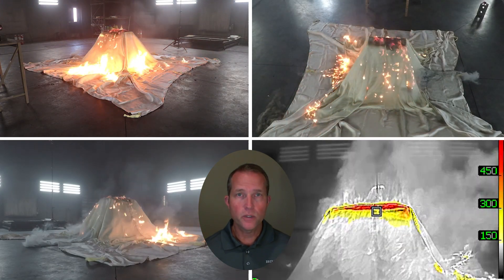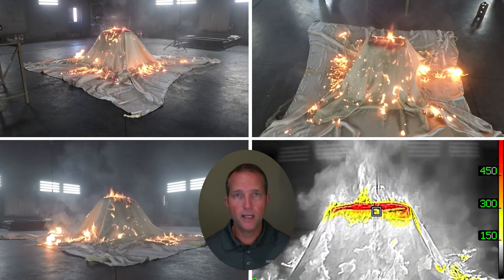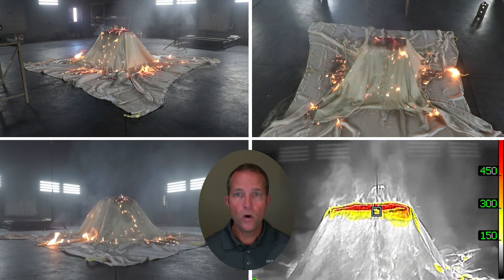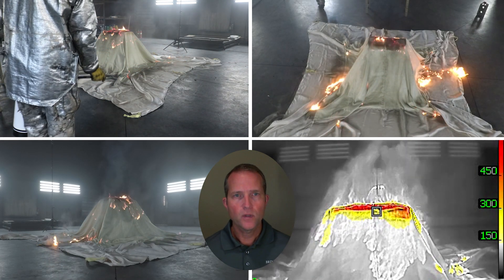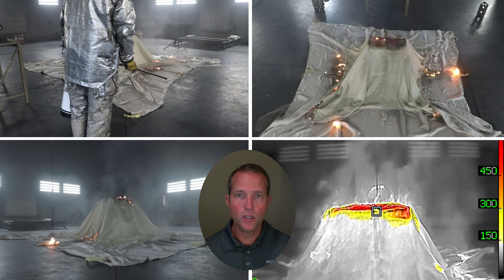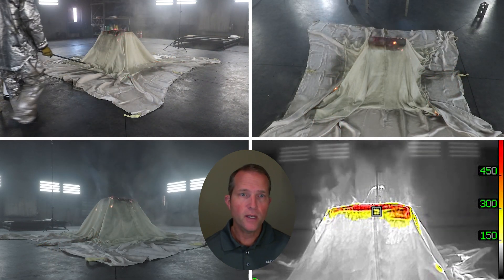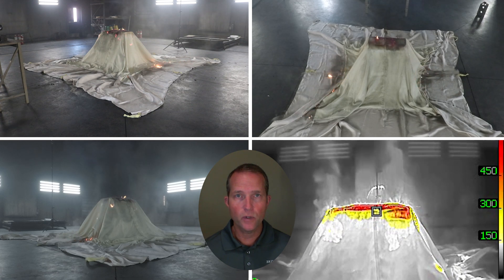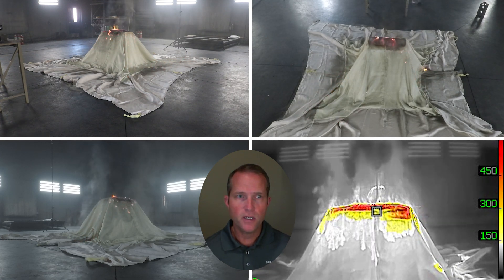The small amount of water needed to extinguish the flames means that firefighters won't necessarily have to drag attack lines into the area, water usage will be much less, and water runoff can be almost non-existent. All these factors add up to a scene that is much easier to manage, contain, and clean up. Since the flames are being fed by the gases being released by the batteries, appropriate respiratory protection and other safety gear should always be used.